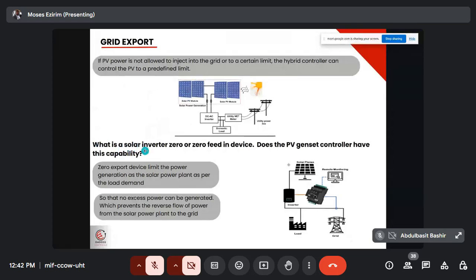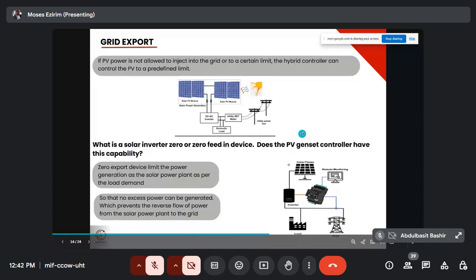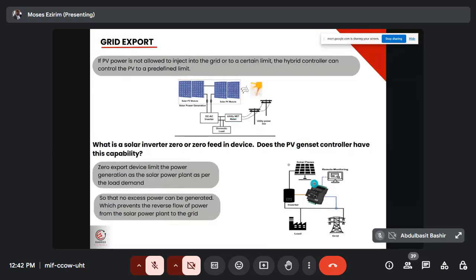Now, what is a solar inverter with zero feeding, or zero export? Does the PV generator controller have this capacity? There's what we call zero exports, meaning there is no excess power, which prevents the reverse flow of power from solar power plants to the grid. So that is just grid curtailment. You can see this is the solar power, this is my inverter, this is the controller.